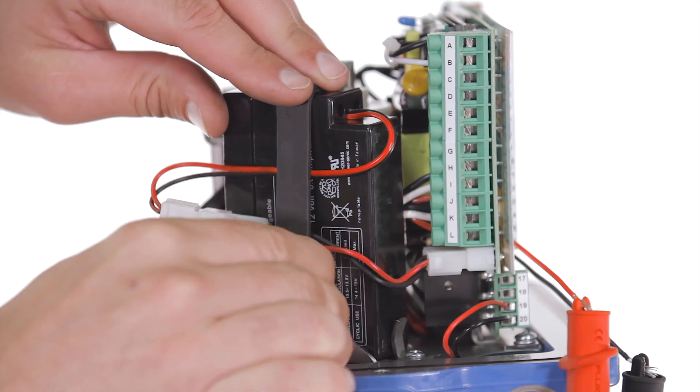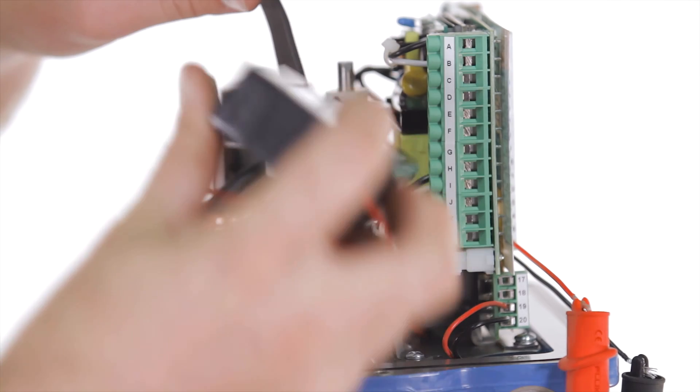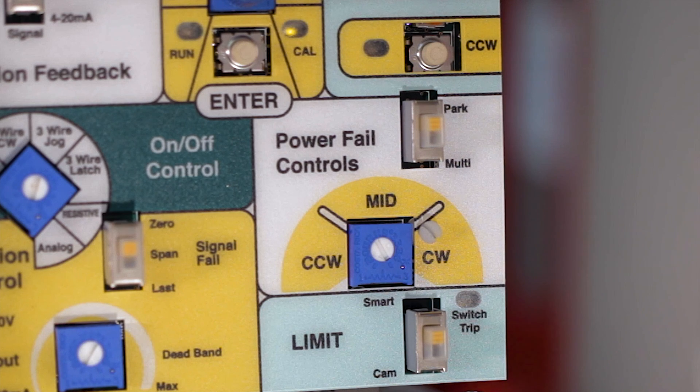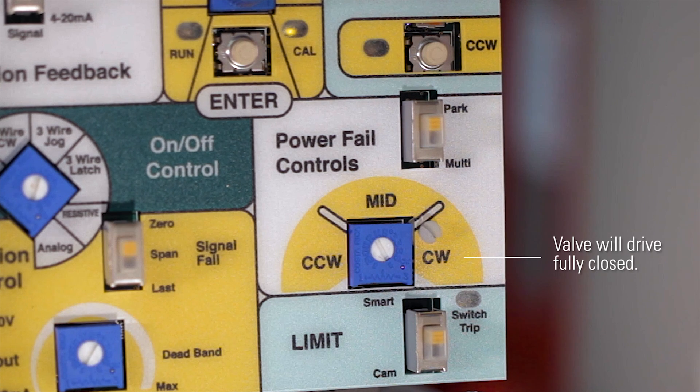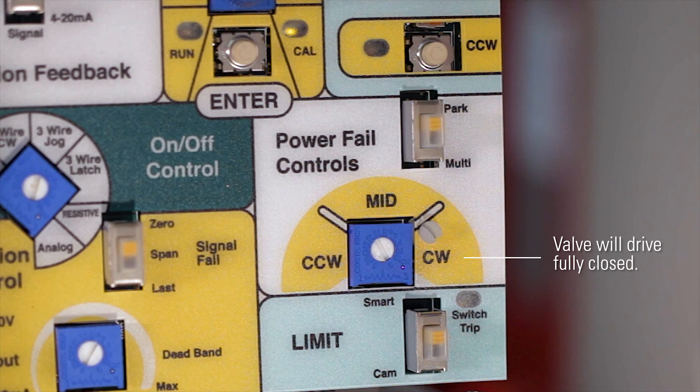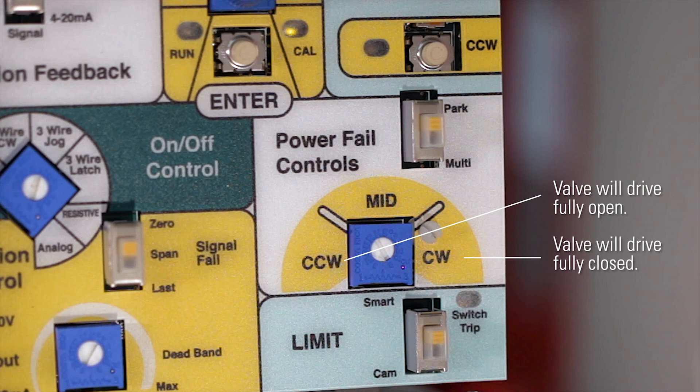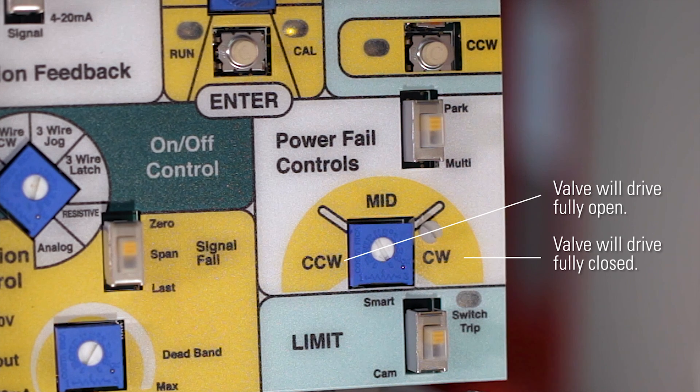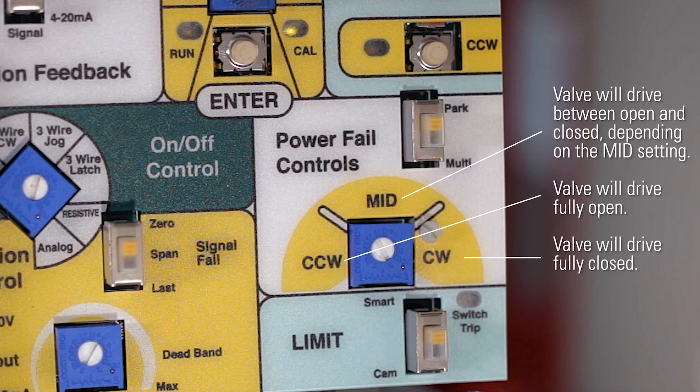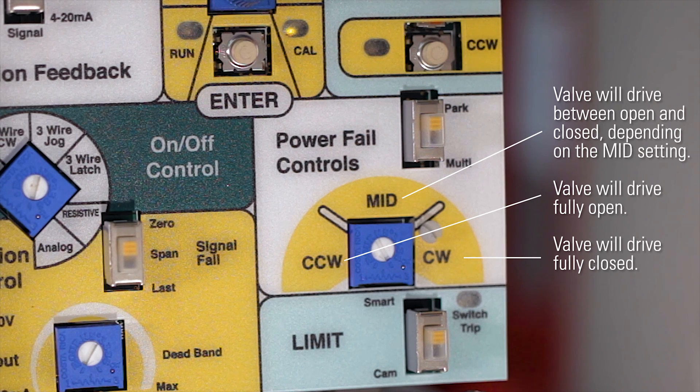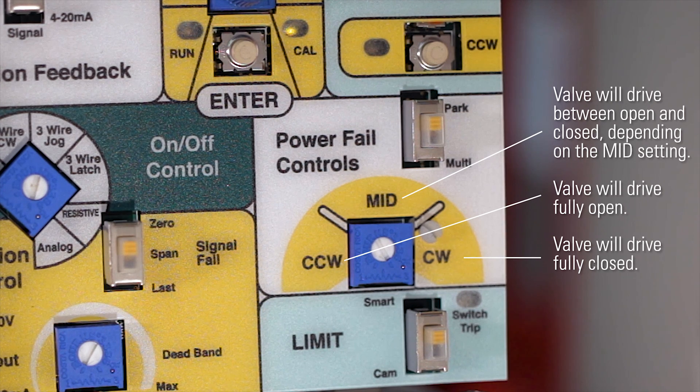The valvecon actuator is also equipped with a backup battery. If power to the actuator is lost, the power fail control switch provides options for the actuator. Clockwise, in which case the valve will drive fully closed. Counterclockwise, in which case the valve will drive fully open. Or mid, in which case the valve will drive between open and closed depending on what your mid position has been set to.